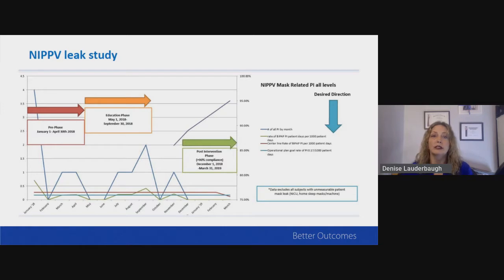Squires and Hinman suggest to tighten the head strap gear slowly if needed to minimize but not get rid of the leak. Lauterbach et al. identified high patient mask leaks of greater than 55 liters per minute as the sole contributing factor that correlated significantly with non-invasive ventilation mask-related pressure injuries. And we also discovered the fewest pressure injuries occurred when you used a range of 25 to 55 liters per minute as a mask leak range.